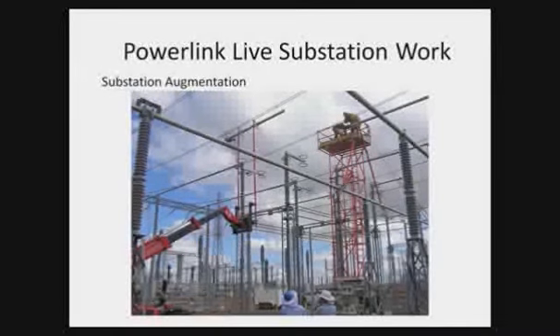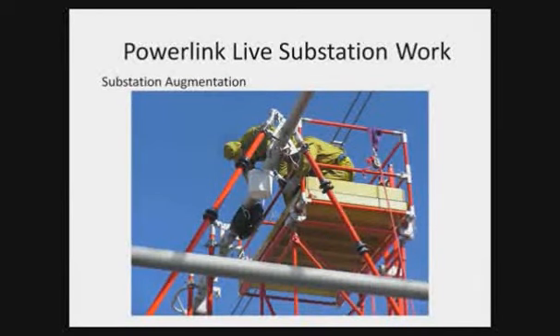Here's a bit of substation augmentation, where we've had to go through and replace all the disconnectors in the whole switch yard to be uprated. Where they were connected directly onto the bus, we had to disconnect and remove sections of bus in order to replace the disconnectors. Here you can see lifting a section of bus out, where the remaining section's held up by an A-frame of hot sticks.